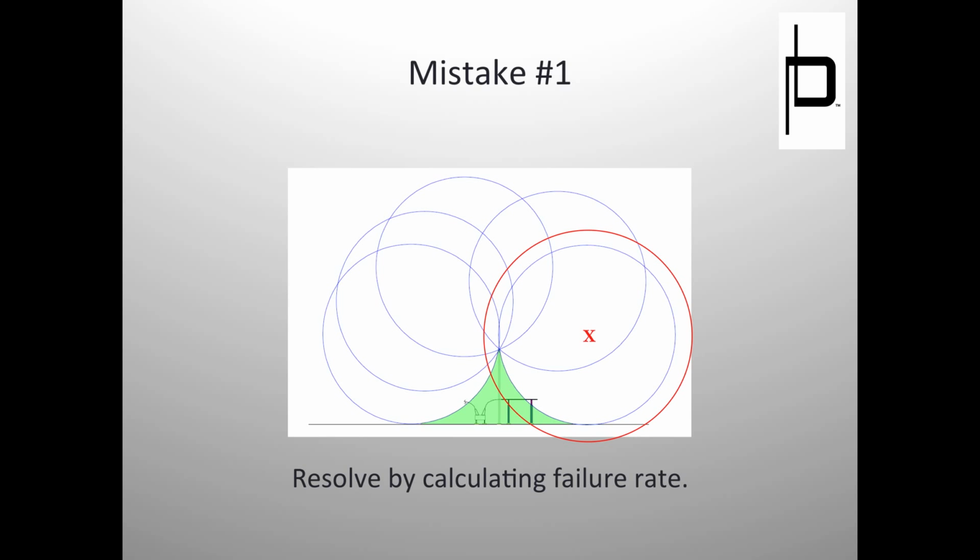You could still have failure of your insulation. We talked about that. Also, this failure rate is based on lightning always striking the mast instead of striking your equipment. And we know that's not always true. So these things will actually reduce the actual protection.